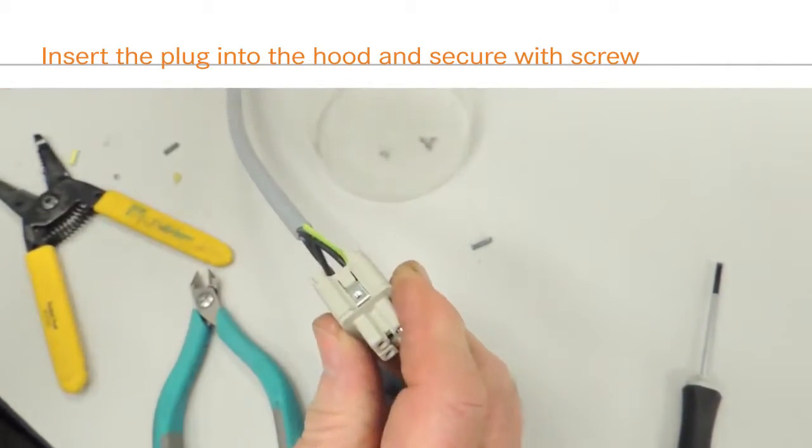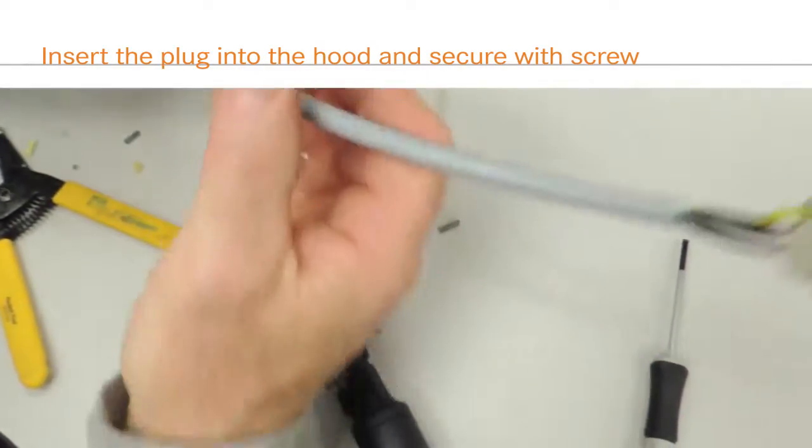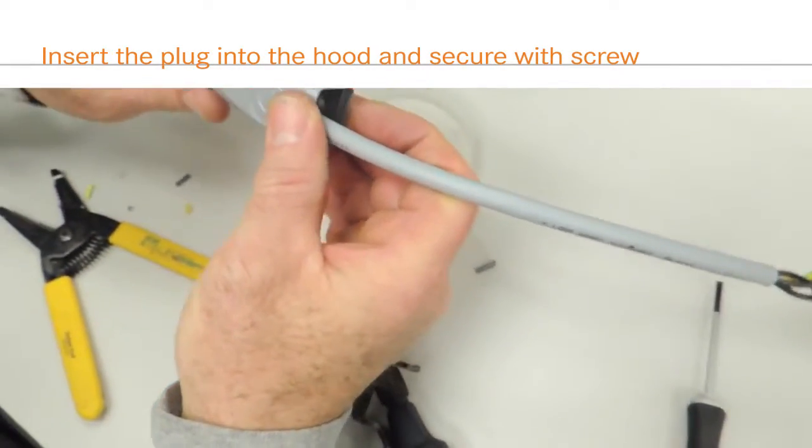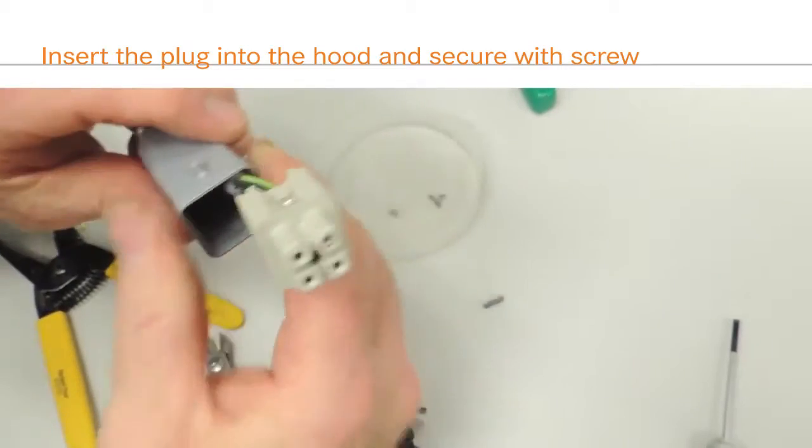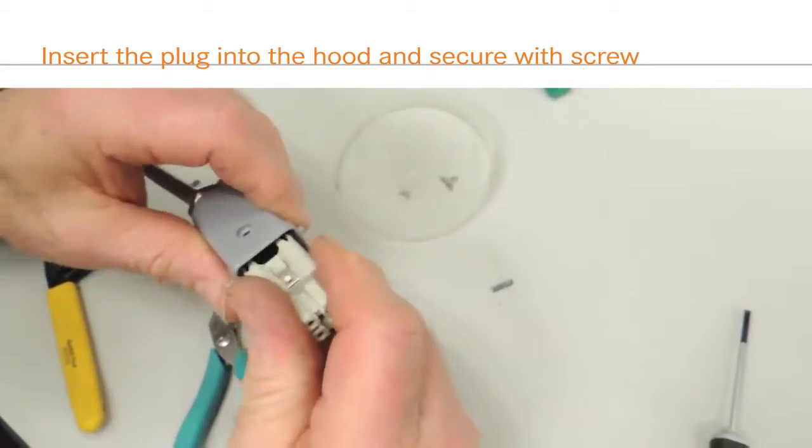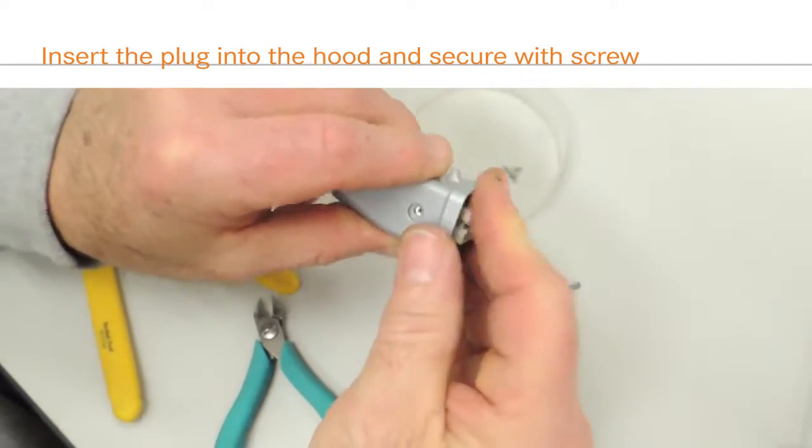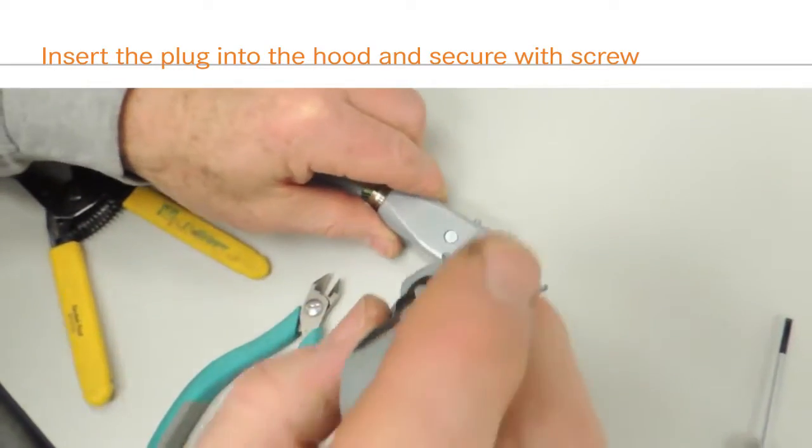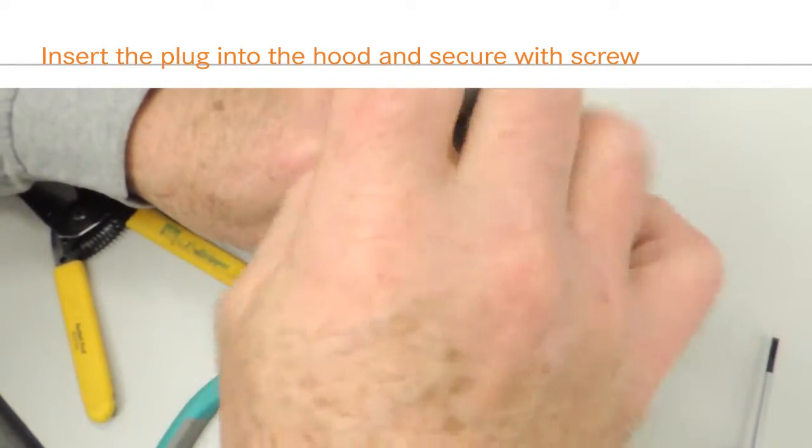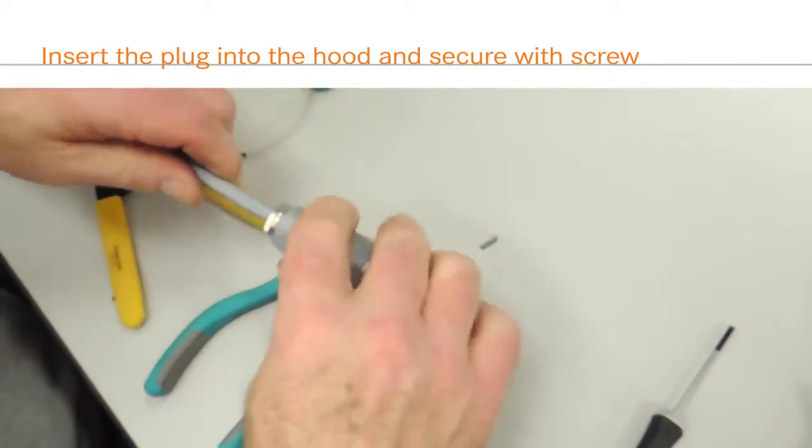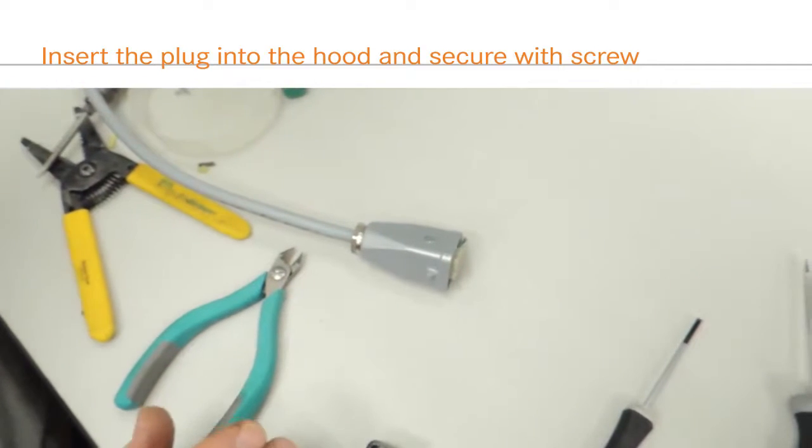The amount of outer jacket to strip is very important for creating a proper environmental seal between the hood, gland, and cable. Outer jacket stripping lengths are influenced by a number of factors, and it is difficult to determine the exact amount to remove in every case. Avoid removing too much of the jacket, as this may prevent a proper seal. For the EPIC HA3 hood, we suggest stripping 25mm of the cable jacket.